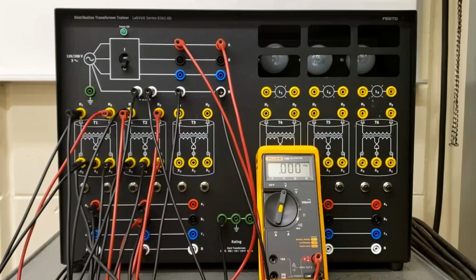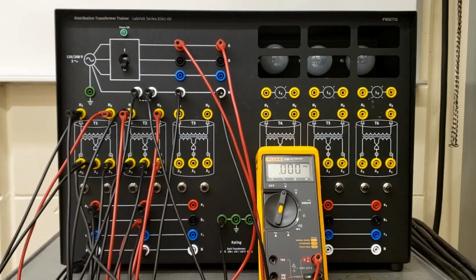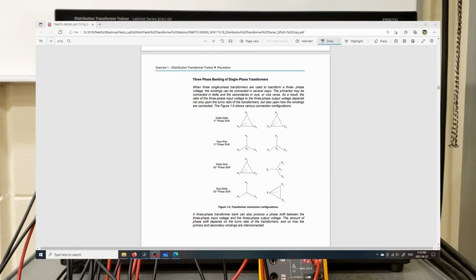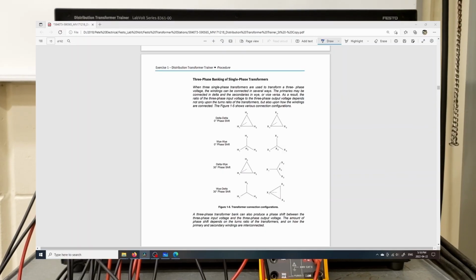On page 6 of the student manual, 7 of the instructor manual, they go through the 3-phase banking of single-phase transformers. So you can have a quick discussion on delta to delta, Y to Y, delta to Y, Y to delta, and then discuss the phase shift. If you have the same configuration, like delta to delta, there's a 0 phase shift. But if you go from one configuration to another, from delta to Y or Y to delta, there's a 30 degree phase shift.